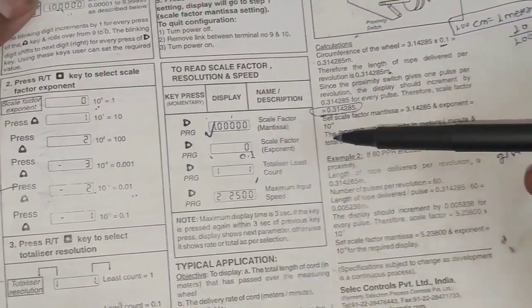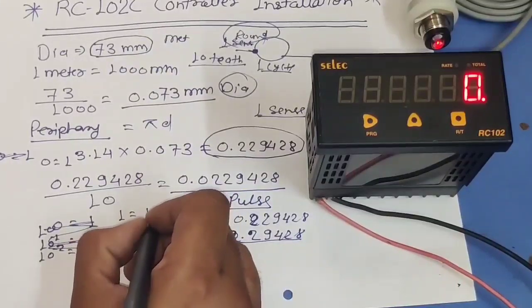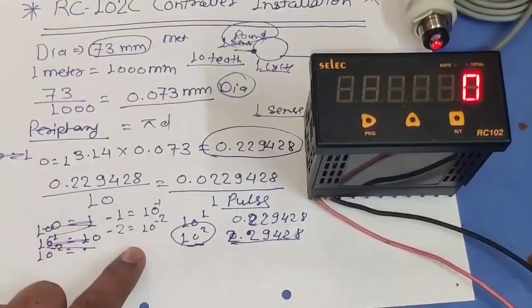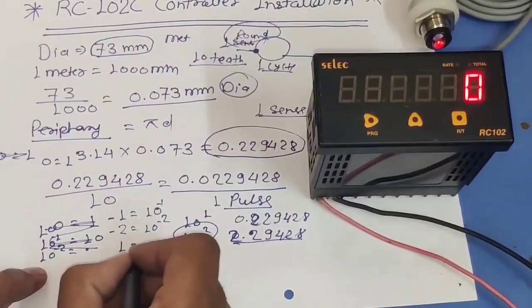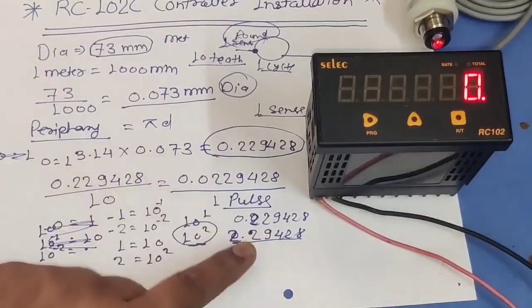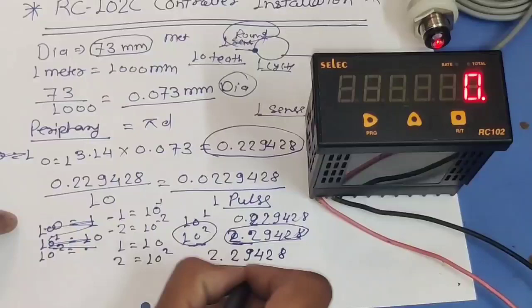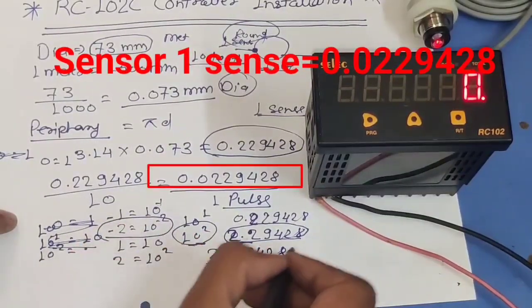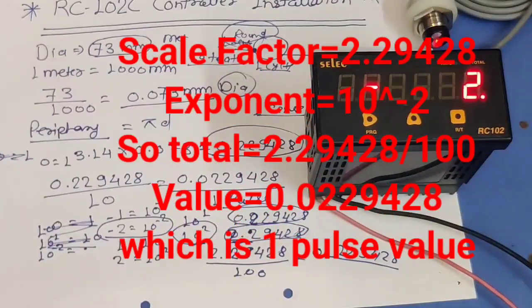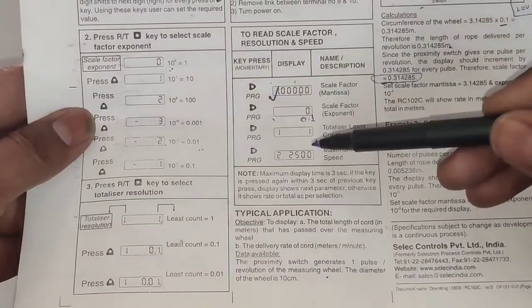Now the second value is scale factor exponent. Because we multiplied by 10 to the power of 2 in the mantissa, in the exponent we divide by 10 to the power minus 2. If you set 0, the value is 1. If you set minus 1, the value is 10 to the power minus 1. If you set minus 2, the value is 10 to the power minus 2. If you set 1 the value is 10, if you set 2 the value is 100. Because we multiplied by 10 to the power 2, we need to set exponent to minus 2, giving us the correct per-pulse value of 0.0229428.